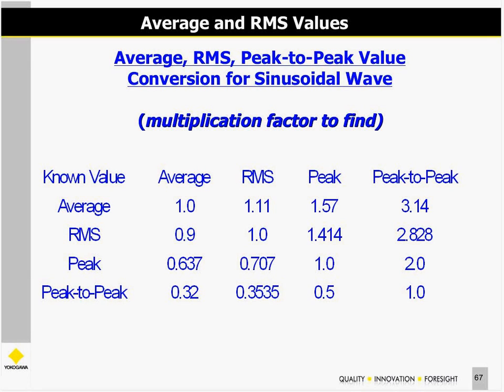So here's what we're talking about. If we know the RMS value and want to get the peak, remember that's the square root of 2, 1.414. This half-cycle average, or mean, is the way the old analog meters used to work, and they had a scale that was given in the RMS value. So if we get the half-cycle average and apply a multiplier of 1.11, that gives us the RMS value. And so this is the function that we're using with this average, or mean, algorithm.